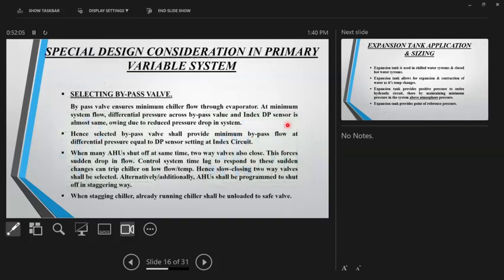Okay. So again, I will repeat: you should not select a bypass valve abruptly. First, check the flow; second, check the flow. Find out what is the minimum flow that the system can generate. What is your minimum requirement? The difference in that is the minimum flow through this bypass valve. And at that flow, the delta P or pressure drop of this valve should be equal to your delta P setting. If you could do this, then your valve is likely to give a very fine control.